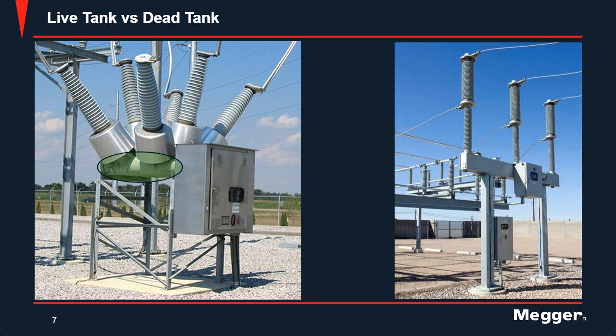So just to go over that again, dead tank, if you look right there, I highlighted the tank. That entire casing is grounded. So all the interrupter, all the linkage, everything inside that tank is surrounded by a grounded shell. There is no live voltage. And theoretically, I'm not telling people to do this, if you walked up to it in a live substation, you could touch the outside of that casing and you would be fine because it is grounded. Now, again, I would not recommend doing that.